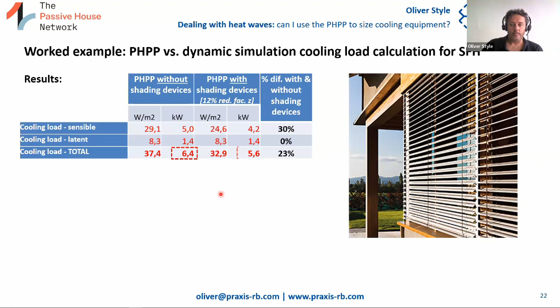If we're talking 20 kilowatts to 7 kilowatts, of course, that's a major difference. And the rule of thumb, at least around here, if you talk to a lot of installers, is 100 watts per square meter. Most installers, if you talk to them and say, what size heat pump do I need here? They're like, 100 watts per square meter. Here's the quote. 100 watts per square meter would mean a 17 kilowatt heat pump for this house. And we don't really need more than 6.5. So that's always the ongoing debate and discussions and arguments that you may have or end up having with different people on site and off site. Anyway, the conclusion here is it's safer just to assume that people don't use the blinds in a perfect way.